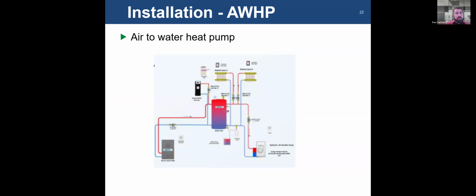We talked a little bit about air to water heat pump installations. These are pretty intricate systems. There's a lot more to these systems than a standard boiler system. You need to make sure that you have your interior space for your buffer tank. You need to make sure you have enough space for your extra pumps, piping, valving, expansion tanks, glycol feeds, whatever you might have for these systems.